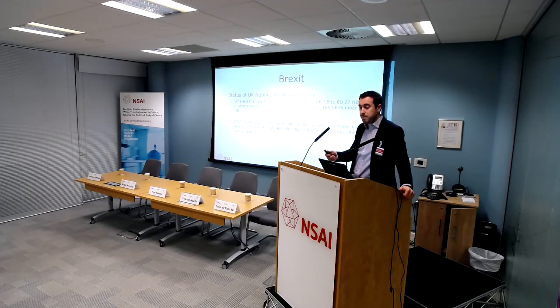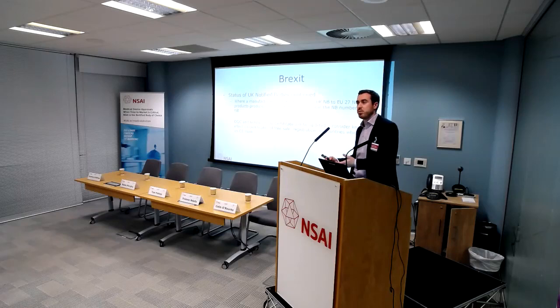Knocking on from that then, if you transfer, some of you I'm sure have been involved in notified body transfer before, the effect it has on your declaration of conformity. Your notified body certificate is obviously going to be changed because it's going to be issued by a new notified body, or at least the same notified body but with a new number. How does that affect certificates of free sale? And again, back to what I said, is your product registered in other jurisdictions on the back of a CE mark? What are the requirements in Australia, for example, if you were to change notified body? Do you just notify the TGA? Do you have to put in a new submission? You need to consider all of this if you are transferring from a UK notified body to an EU 27 notified body.